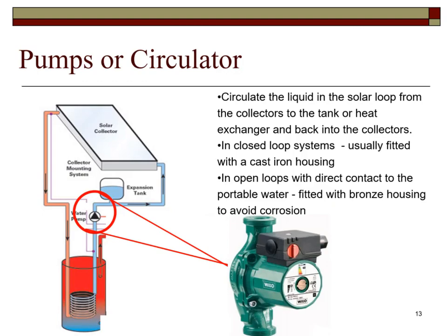Selecting the right pump for the solar thermal system is not as simple of a task. The choices are many: AC or DC powered, bronze, stainless steel, iron or plastic, high, medium, or low head pressures. Pumps used in solar thermal systems are also referred to as hot water circulators. Pumps are made of 3 parts: a motor, impeller, and housing. The motor rotates the impeller to move the liquid by centrifugal force.